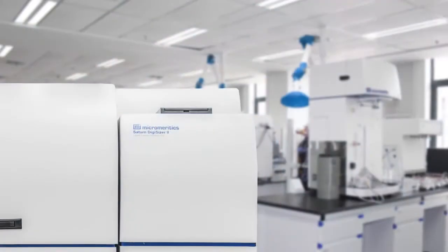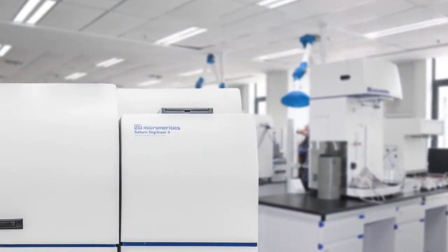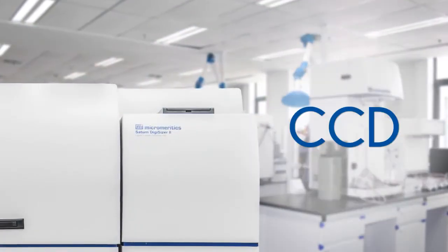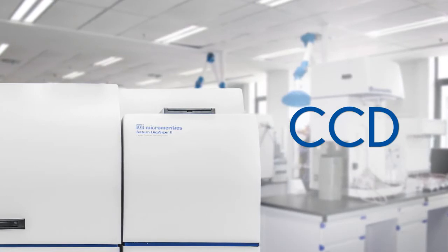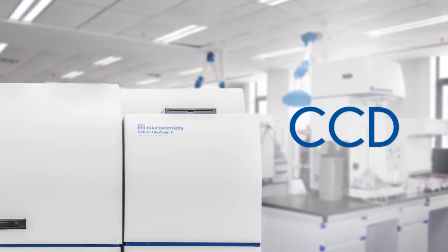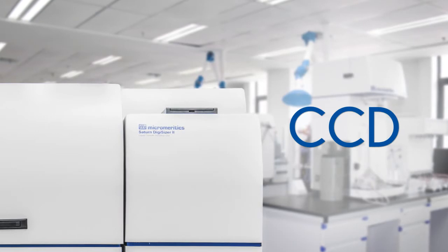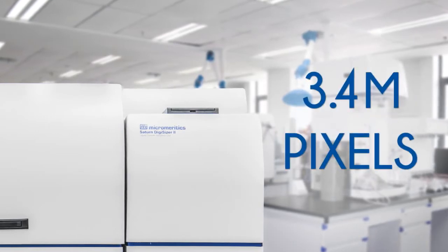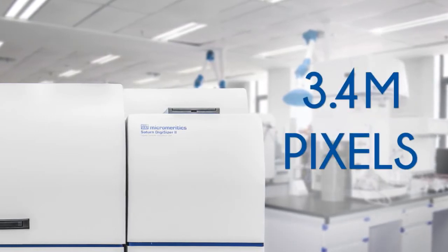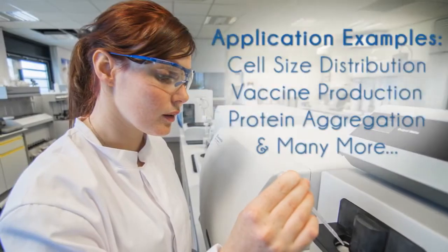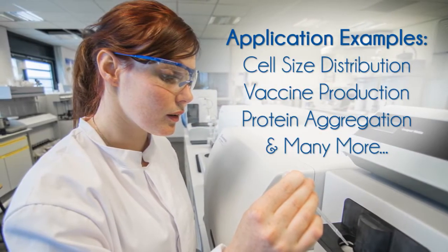The Saturn DigiSizer 2 by Micromeritics uses a CCD detector and a laser that moves at 14 different angles to capture as much of the scattered light as possible. The CCD has over 3.4 million pixels, or detector elements, at each angle for a total of 47.6 million pixels.